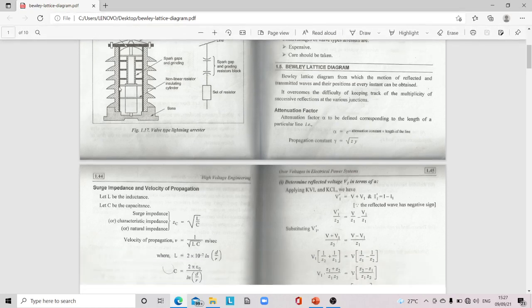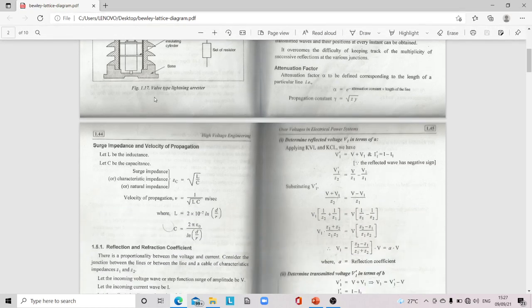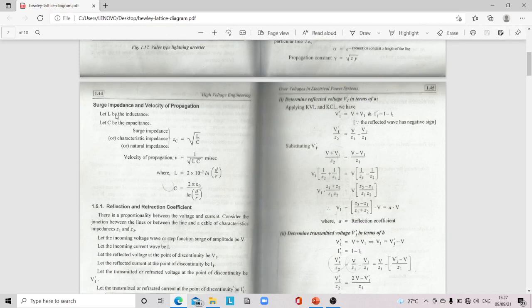The surge impedance Z_C = √(L/C) and velocity of propagation v = 1/√(LC) meters per second, where L = 2×10⁻⁷ log(d/r) and C = 2πε/log(d/r).